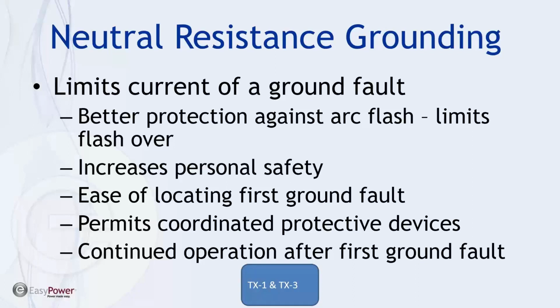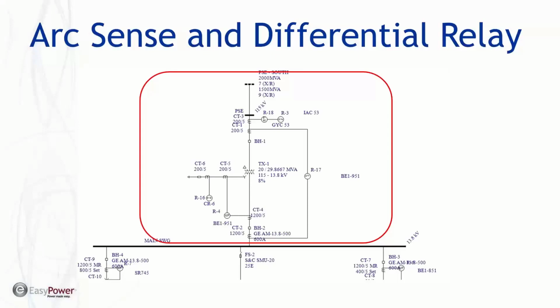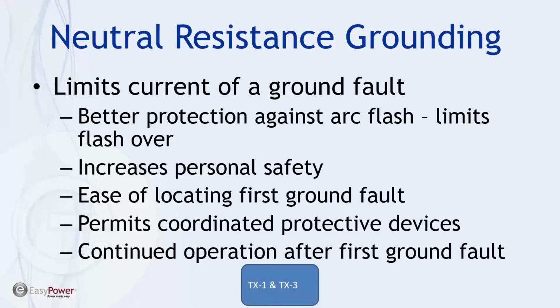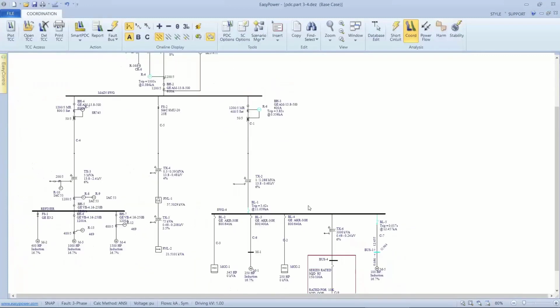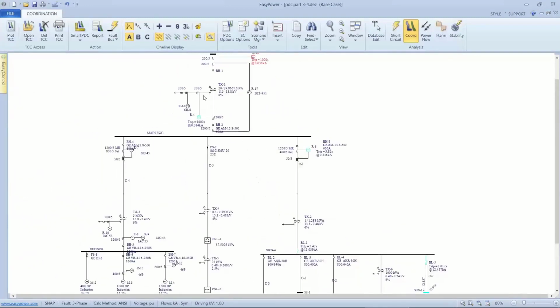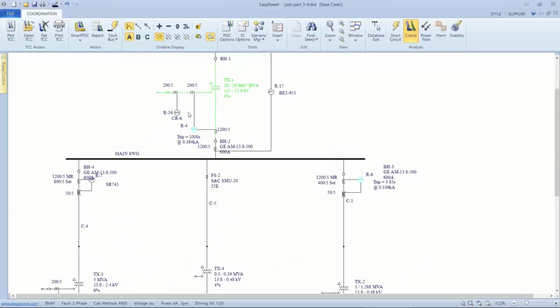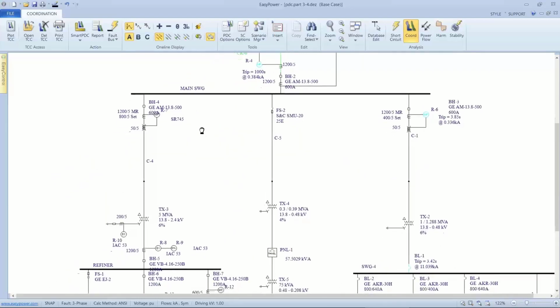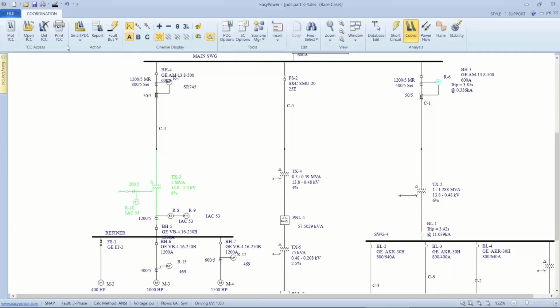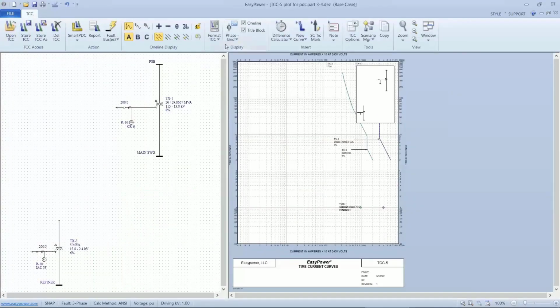So the neutral resistance grounding does permit coordinated protective devices, and it does allow you to continue to operate after the first ground fault, based upon the fact that there's a limited amount of current. So before I get there, let's jump into EasyPower and see if we can see this. So basically, we've got two transformers that have resistance grounding. This is protected by, in this case, relay 16. So we're going to set up this 2. Let's go ahead and plot it with this 2. Plot the TCC curves and expand it a little bit.